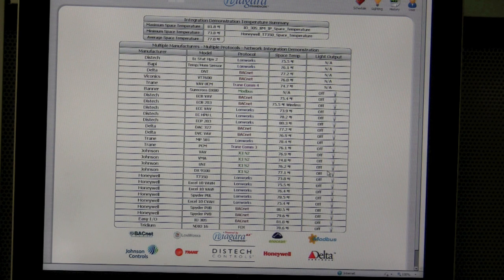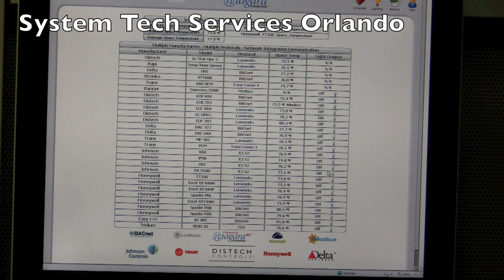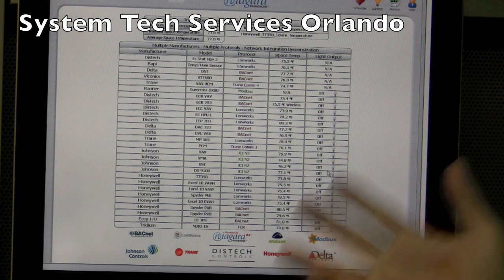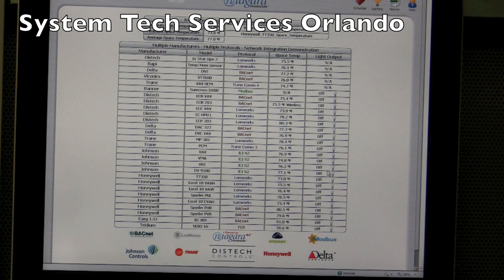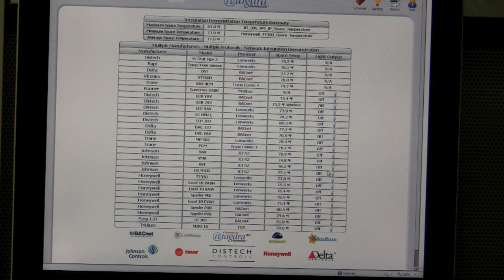I click the light switch and all the lights turn on from all these manufacturers. I'm also reading space temp from all these manufacturers. What we do is we normalize the data — it doesn't matter who made it or what protocol it's talking. We just bring it in, and it's a data point on their front end.